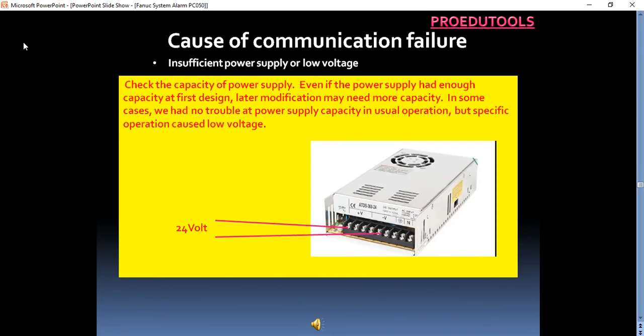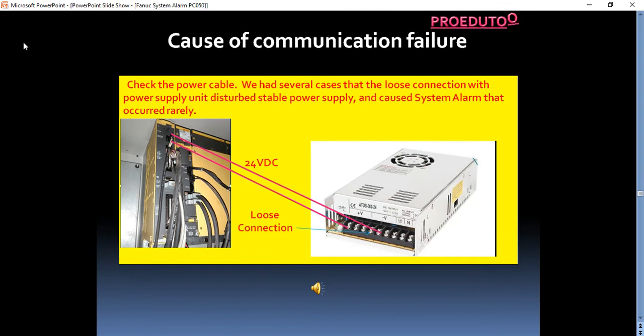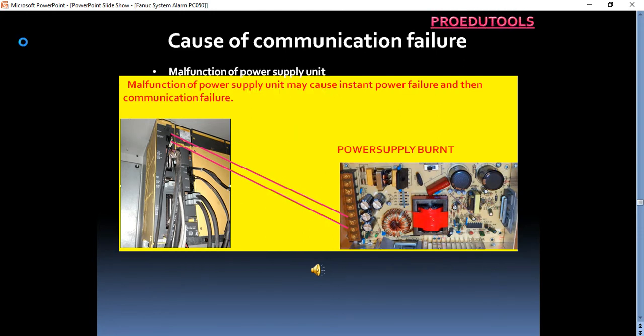Insufficient power supply or low voltage. Check the capacity of power supply. Even if the power supply had enough capacity at first design, later modification may need more capacity. In some cases, we had no trouble at power supply capacity in usual operation, but specific operation caused low voltage. Insufficient connection to power supply, check the power cable. We had several cases that the loose connection with power supply unit disturbed stable power supply and caused system alarm that occurred rarely.